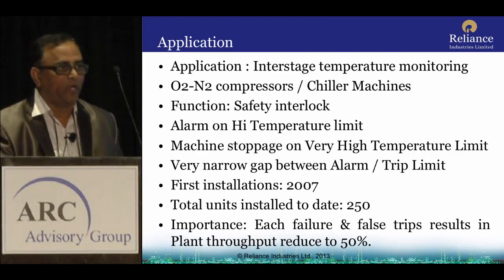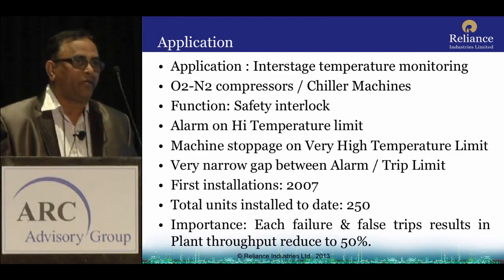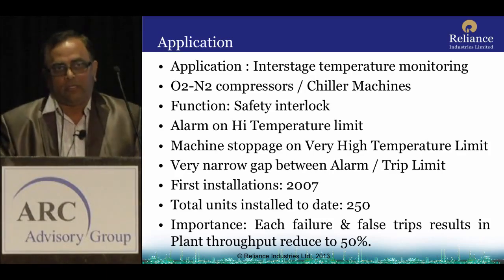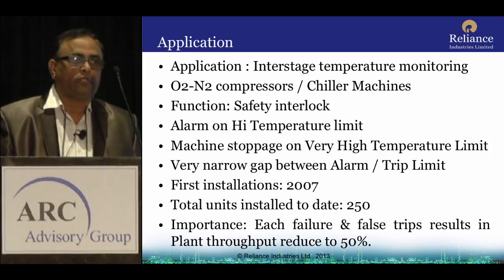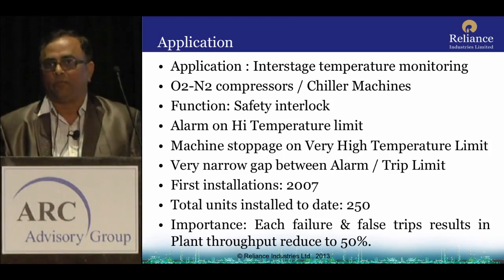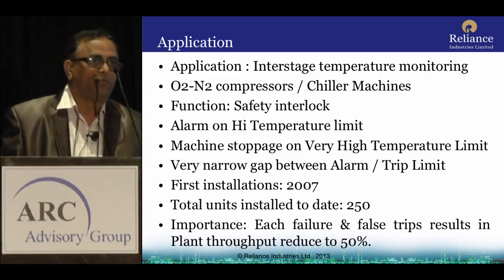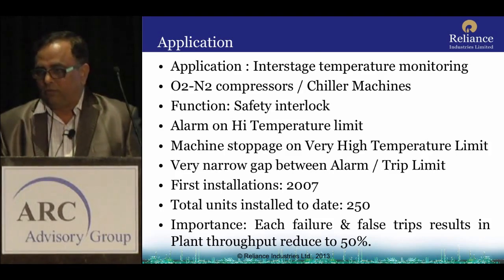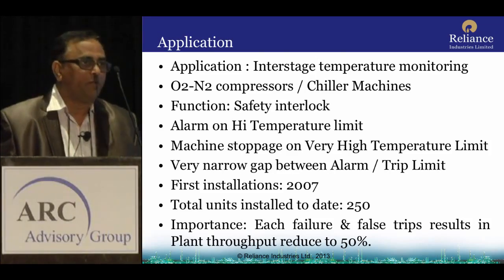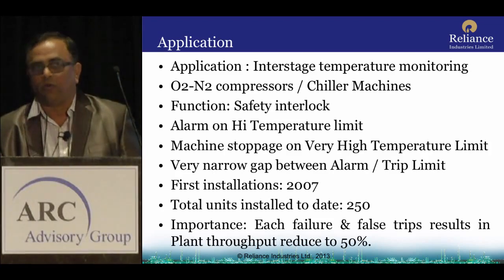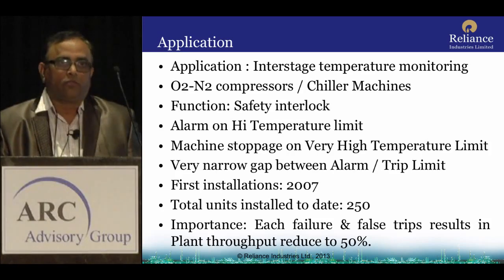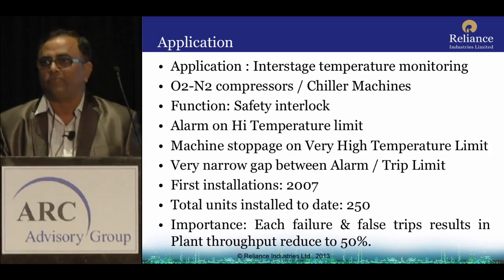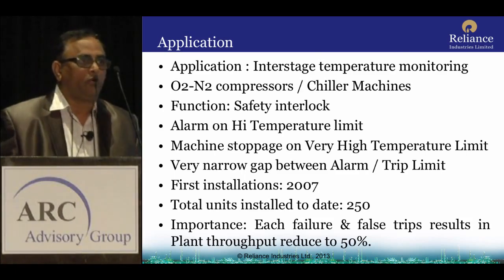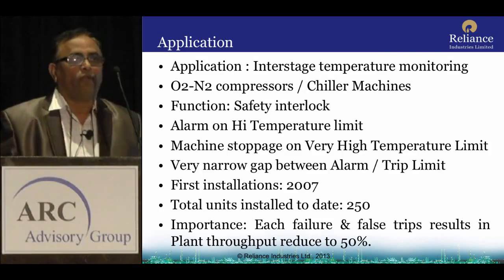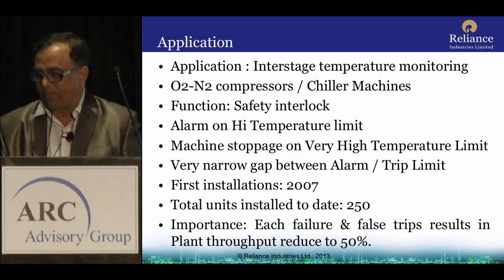Now coming to the application where we have done some value addition as far as the smart device in the field is concerned. The application is particularly in the oxygen and nitrogen compressor we had in the plant to compress the oxygen at a higher pressure for the process application, for example the ethylene oxide reactor. The function of the particular device was the safety interlock, and there are the high alarms and the very high trip for the compressor stoppage. It's a very narrow deadband as far as the alarm and trip set points are concerned. It is particularly 184 degrees centigrade and 187 degrees centigrade. It's hardly 2 or 3 degrees centigrade.